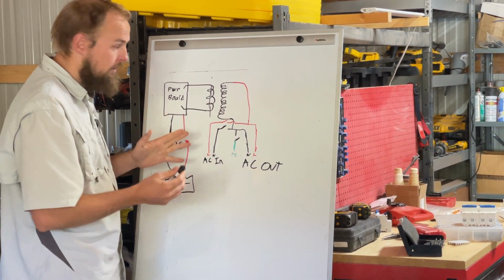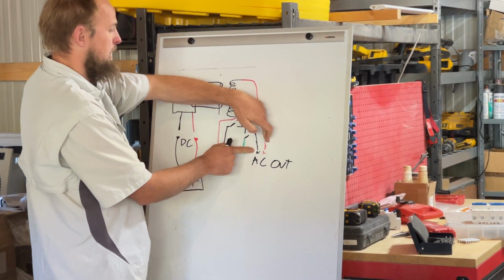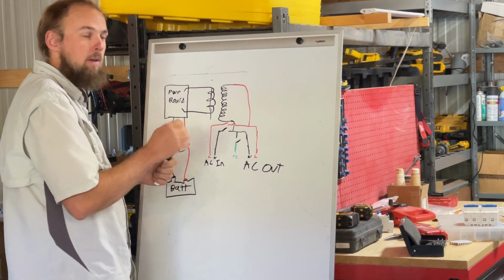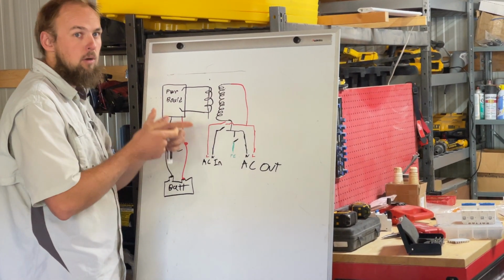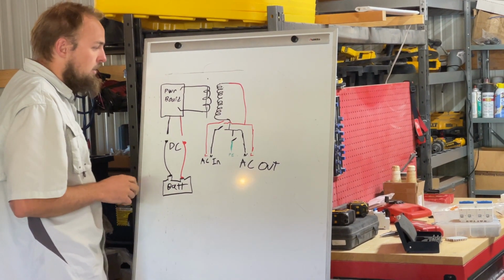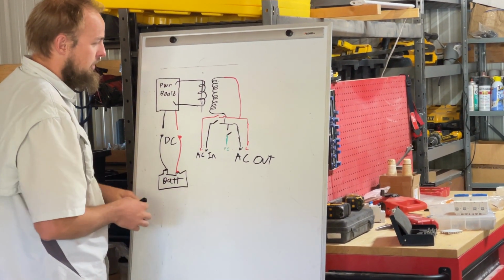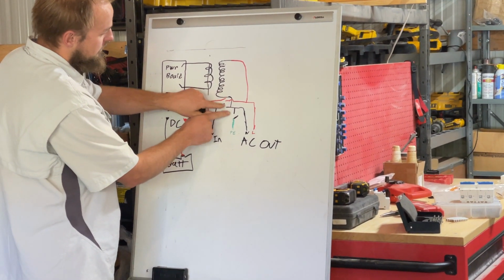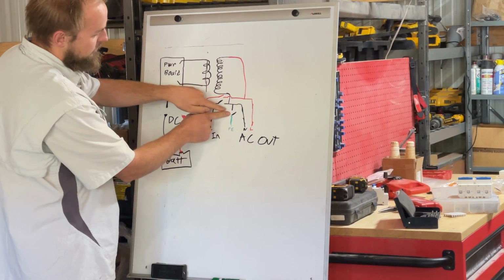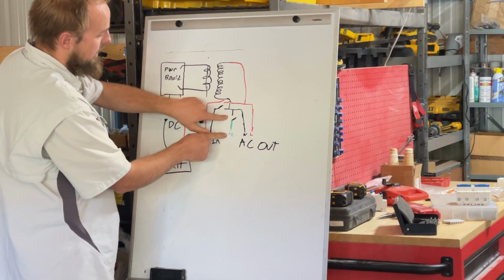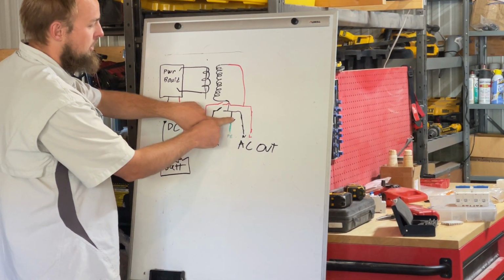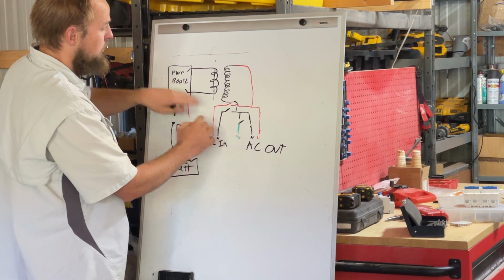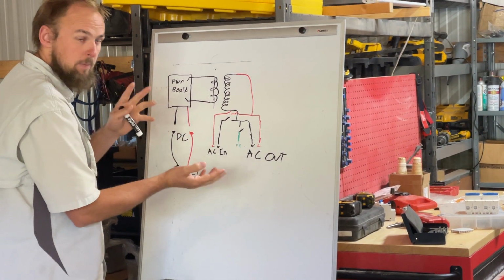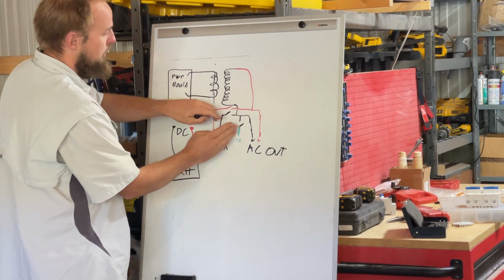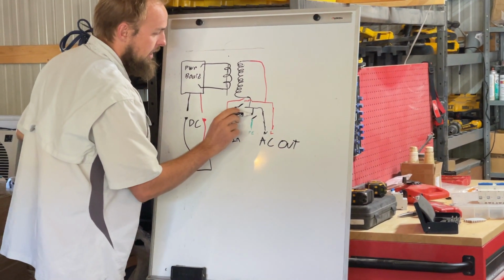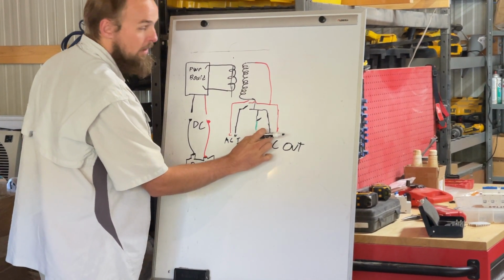When the inverter is turned on, you'll have 120 volts between neutral and line. And in that case, you do not want to put your meter in continuity mode, because meters in continuity mode do not work when there's voltage applied. And there's a little bit more in depth on the topology. When the inverter is turned off, on the Victron specifically, there's this contactor that connects neutral to ground, potential earth. And when it's off, that contactor is open, so there's no continuity here. When you turn the whole system on, you can change the programming, but the default programming is that if there's no AC input, that contactor closes, and then now there would be continuity between ground and neutral.